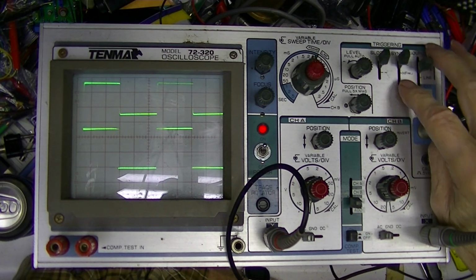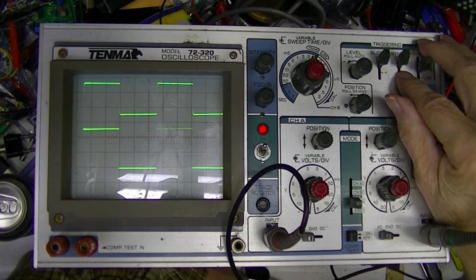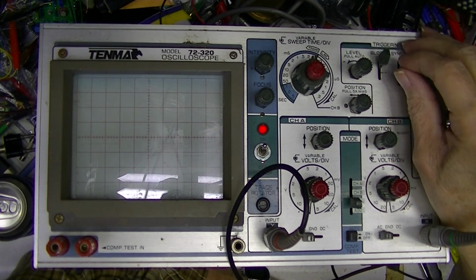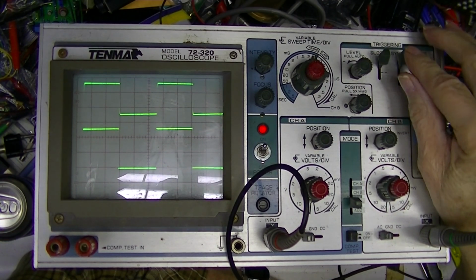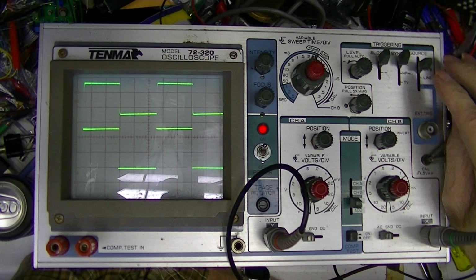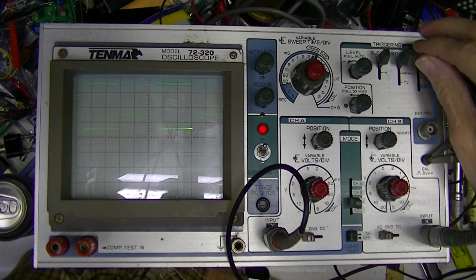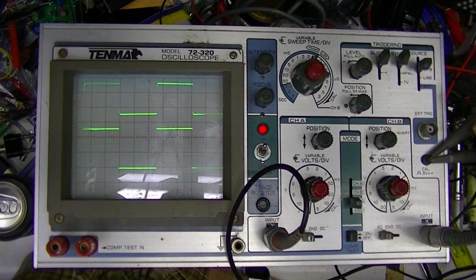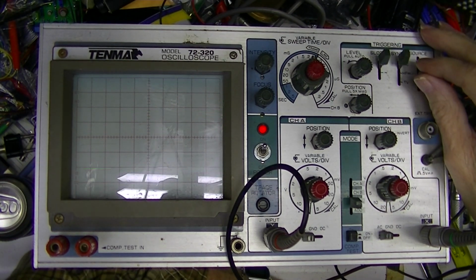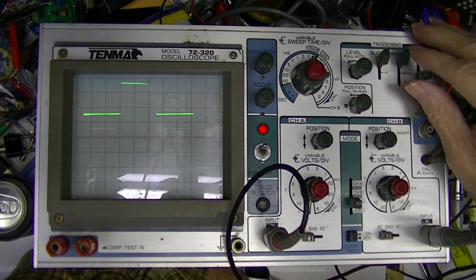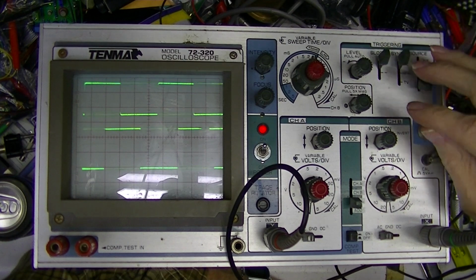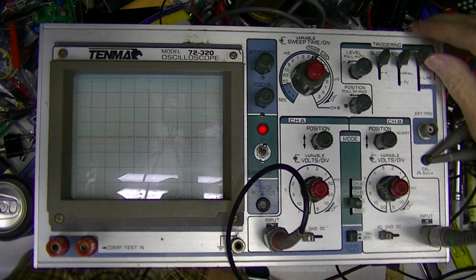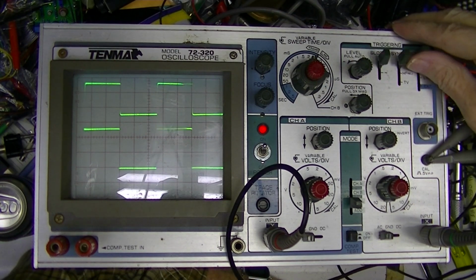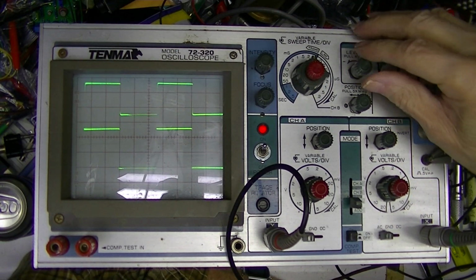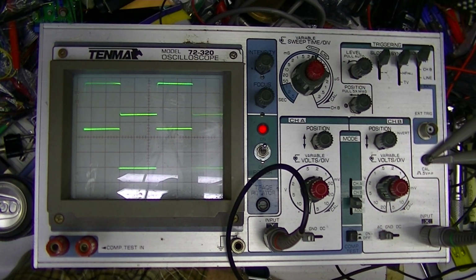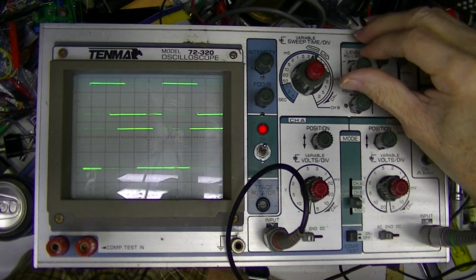This is normally left in the AC position. There are situations where you want to synchronize off something else. So, this decides if we're syncing off of channel A or channel B, or the 60 hertz line frequency, which you probably won't use, or some external sync, which is entered here. So, leave these three switches up, leave this out, and at least it may not be synced, but there'll be green lines.